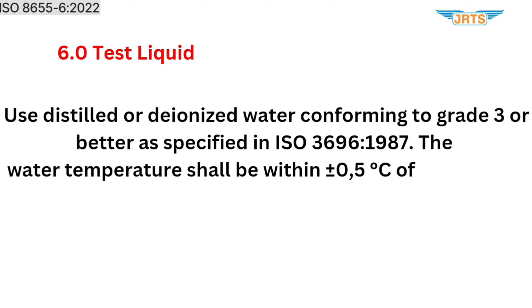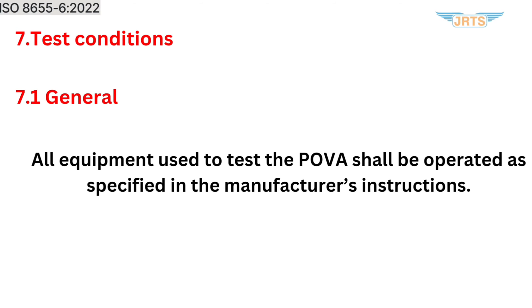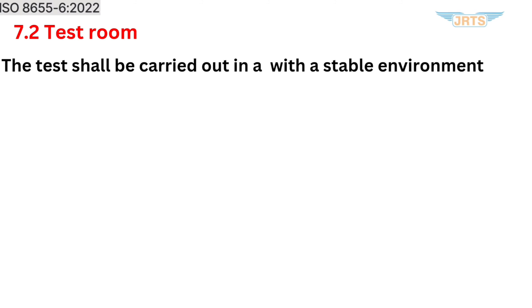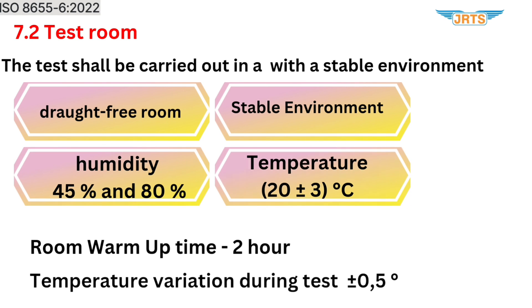The water temperature shall be within 0.5 degrees Celsius of ambient air temperature. Section 7, Test Conditions: All equipment used to test a POVA shall be operated as specified in the manufacturer's instructions. Section 7.2, Test Room: The test shall be carried out in a draft-free room with a stable environment — humidity between 45% and 80%, temperature 20 plus or minus 3 degrees Celsius, room warm-up time 2 hours, and temperature variation during the test within 0.5 degrees Celsius.